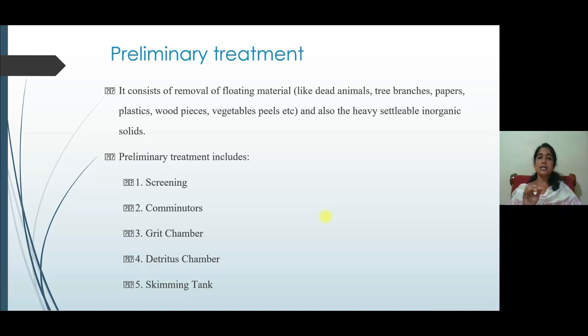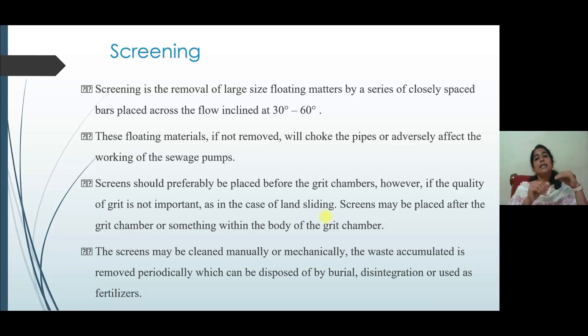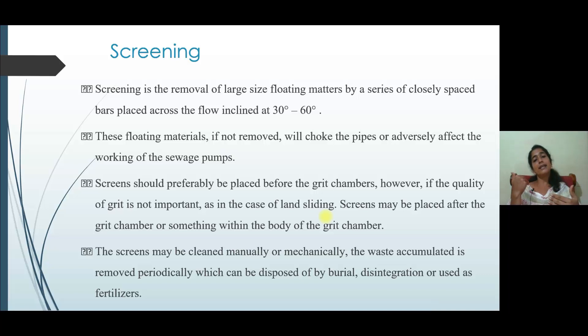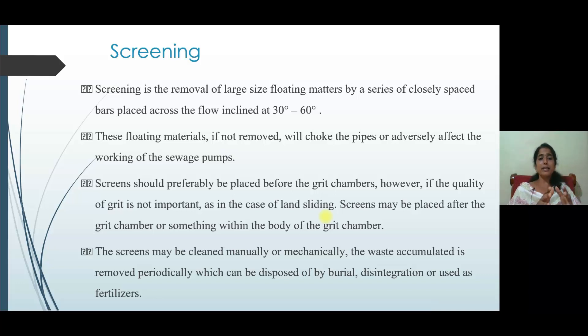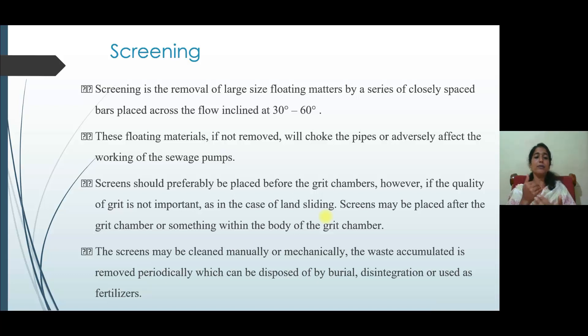Screening is basically a filtration process using mesh-type or bar screens. It is the removal of large-sized floating matter by a series of closely spaced bars placed across the flow channel, inclined at 30 to 60 degrees. This inclination is provided along with bar racks for easy cleaning. These floating materials, if not removed, will choke the screens and affect the efficiency of the treatment plant, as well as the working of the sewage pumps. The screen should preferably be placed before the grit chamber.